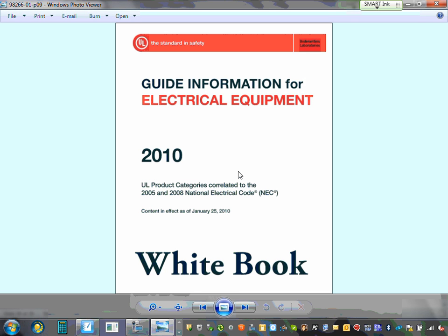Go to the white book, it will tell you which page to find the listing for that section, and it's UL 5673, basically whatever the number is. It will tell you the UL listing number for that piece of equipment. So they made it really easy to correlate the NEC code book with the UL listing, to make it easier for engineers to verify that this equipment is what it says it is.